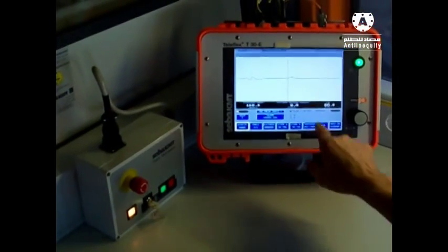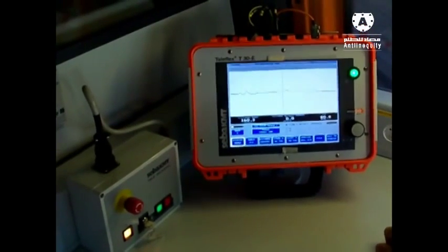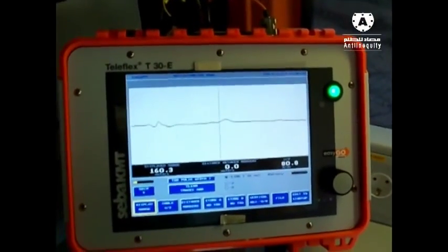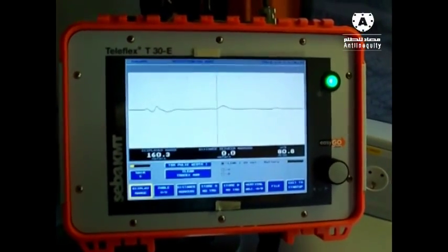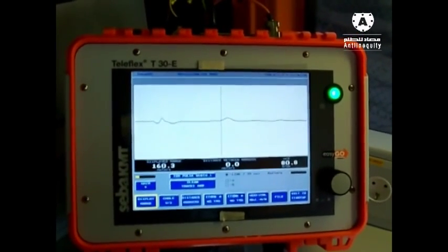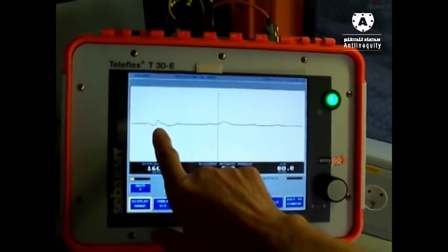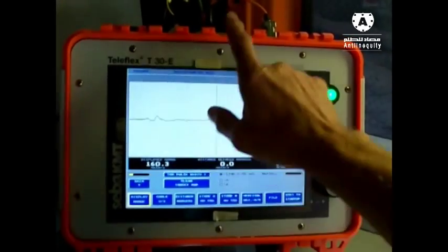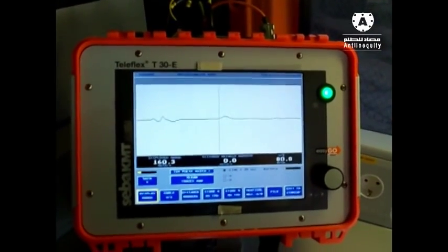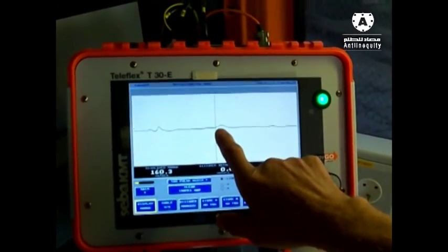The first is we have to adjust our picture. If you know the real cable length, you must adjust first the display range. In our case now we have connected at our cable from the test van cable drum only a spark gap. That means our cable is not longer than 50 meters. What we see now on the screen is, this is our beginning impulse. This is impedance change from here through the system and the connection point of our cable drum, high voltage cable drum, and this should be our cable end.